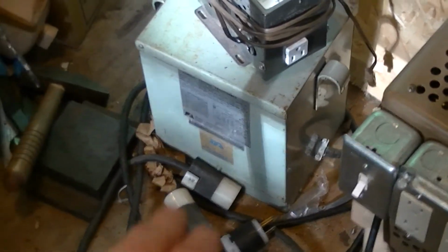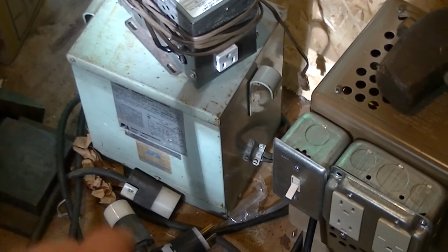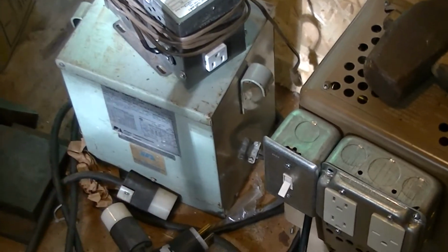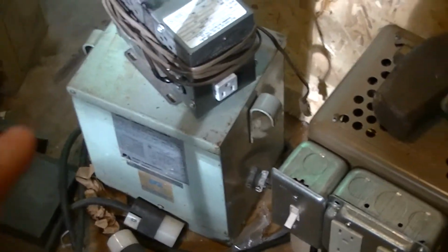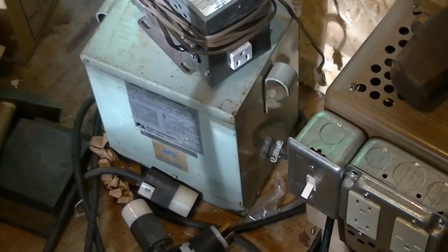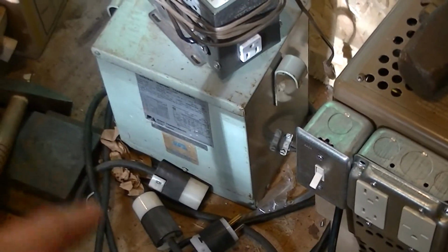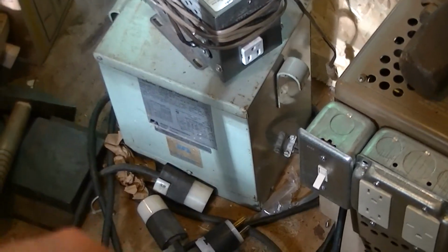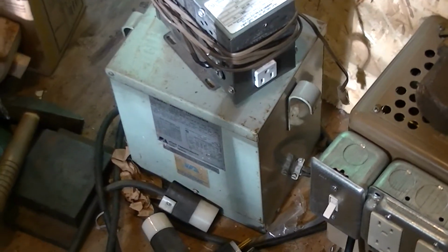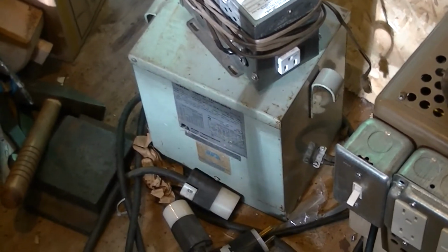In the case of this one, it has a primary winding that's actually a pair of 240 volt windings, nominal, but technically 252 volt windings, tapped at 240 volts and 228 volts. Wired in parallel, it's good for 228 volts, 240 volts, or 252 volts in, or in series, 456 volts, 468 volts, 480 volts, 492 volts, or 504 volts.